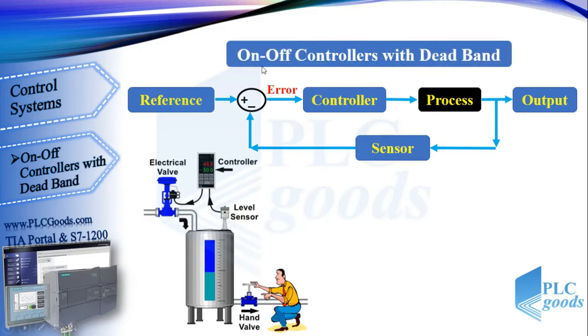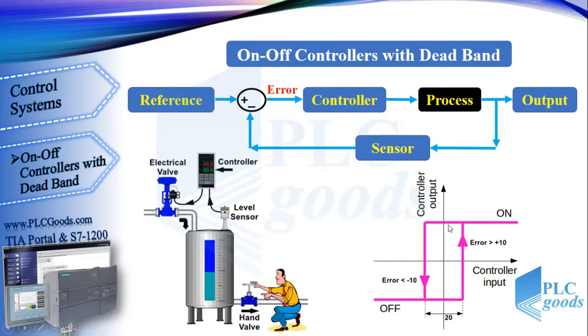This diagram shows the operation of the on-off controller. This controller opens the filling valve when the error is positive, otherwise its output is off. The main problem is when the error is close to zero, because in the presence of disturbances such as fluctuations in the liquid, the controller output switches between on and off continuously. To solve this problem, we can use on-off controllers with a dead band. The controller output is off until the error reaches 10 centimeters. After that, small disturbances cannot turn off the output immediately, because the output stays on until the error reaches minus 10 centimeters. So with this, small disturbances cannot change the output states. Based on the process and disturbances, we can change this width.